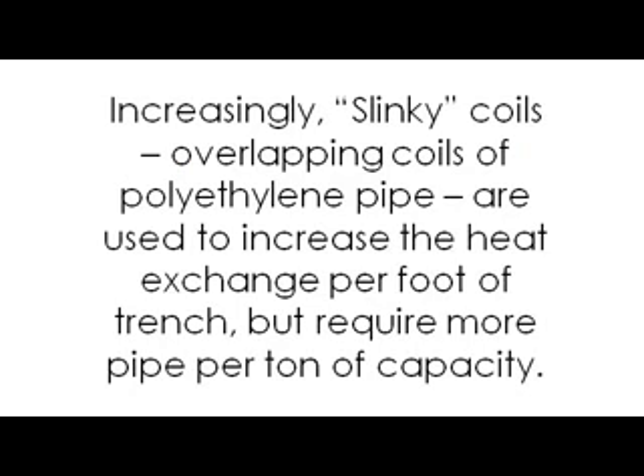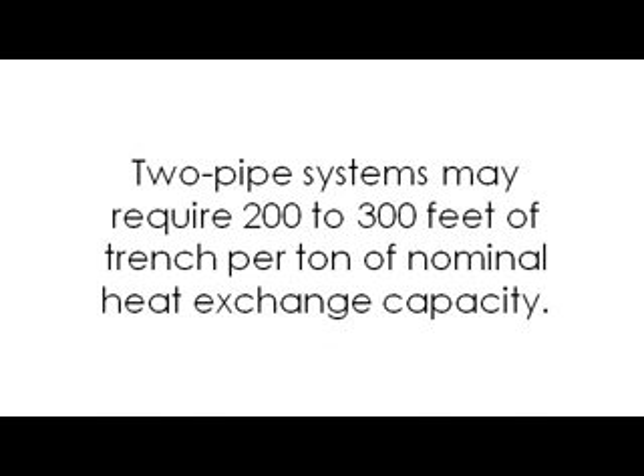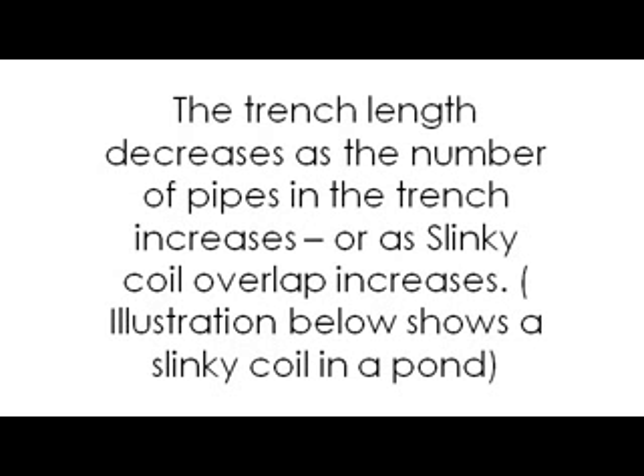Increasingly, slinky coils, overlapping coils of polyethylene pipe, are used to increase the heat exchange per foot of trench, but require more pipe per ton of capacity. Two-pipe systems may require 200 to 300 feet of trench per ton of nominal heat exchange capacity. The trench length decreases as the number of pipes in the trench increases, or as slinky coil overlap increases. Illustration below shows a slinky coil in a pond.